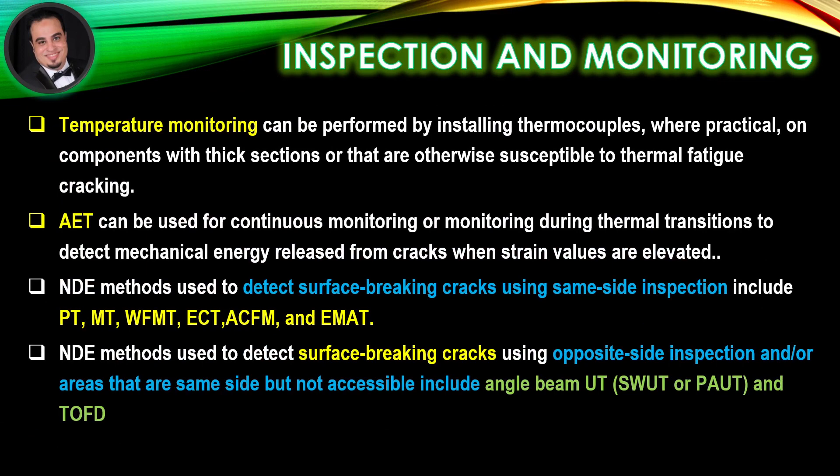Inspection and monitoring: temperature monitoring can be performed by installing thermocouples where practical on components with thick sections or that are otherwise susceptible to thermal fatigue cracking. Acoustic emission testing can be used for continuous monitoring or monitoring during thermal transitions to detect mechanical energy released from cracks when strain values are elevated.